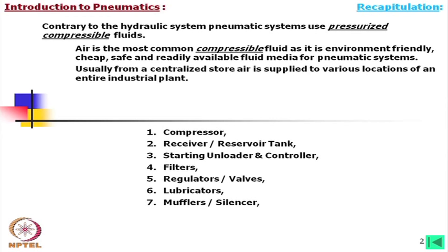In the case of fluid, oil or liquid returns to the tank, and that is not that noisy in comparison to gases. When gas, air particularly, is released, it is released to the atmosphere. In that case, it makes a noise. So, essentially we need a silencer at the end, but we also need a silencer when it is entering the system, I mean the utilization end. That silencer is usually called an inline silencer.